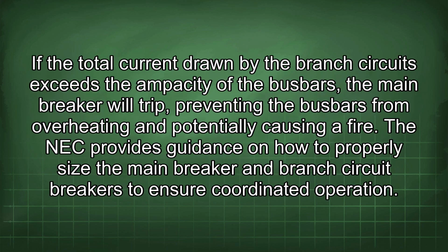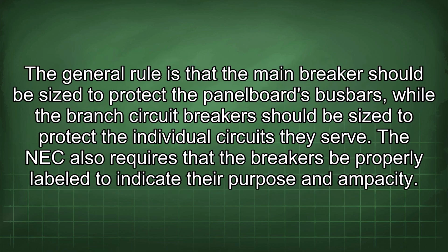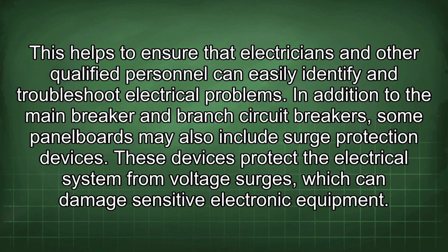If the total current drawn by the branch circuits exceeds the ampacity of the busbars, the main breaker will trip, preventing the busbars from overheating and potentially causing a fire. The NEC provides guidance on how to properly size the main breaker and branch circuit breakers to ensure coordinated operation. The general rule is that the main breaker should be sized to protect the panel board's busbars, while the branch circuit breakers should be sized to protect the individual circuits they serve. The NEC also requires that the breakers be properly labeled to indicate their purpose and ampacity. This helps to ensure that electricians and other qualified personnel can easily identify and troubleshoot electrical problems.